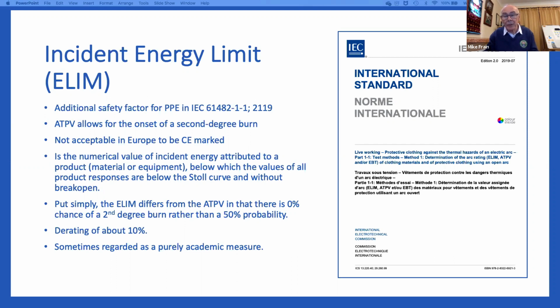She created a Stoll curve where there's a 50% chance with an ATPV; now there's a 0 chance. It's because all the values are below that Stoll curve, so there isn't any chance of a second degree burn. So put simply, ELIM differs from ATPV in that there's a 0 chance of a second degree burn, rather than a 50% probability. But when it's applied to a garment, I understand from people I know that this additional safety factor would lower it by about 10%, derating for the garment. So it could be 10% heavier, I suppose. That's the other way of looking at it.